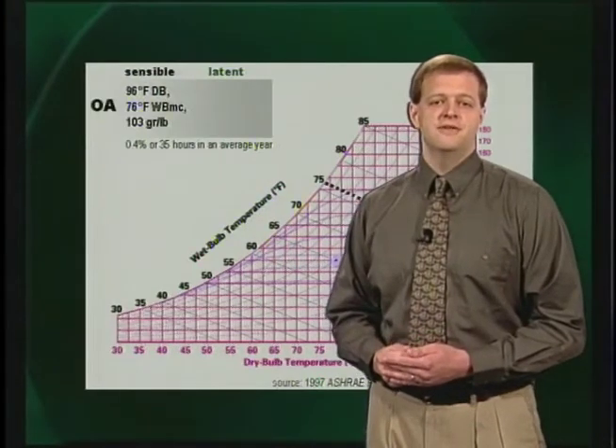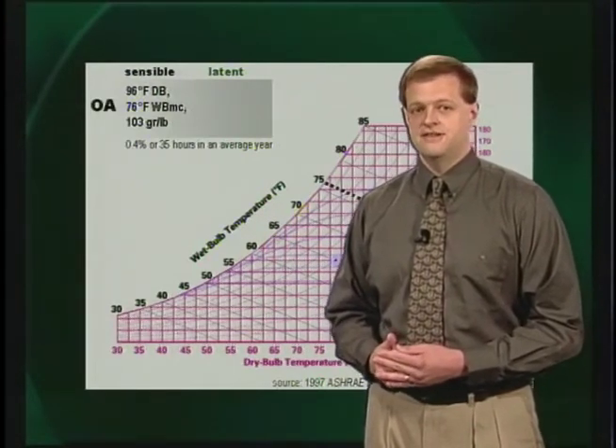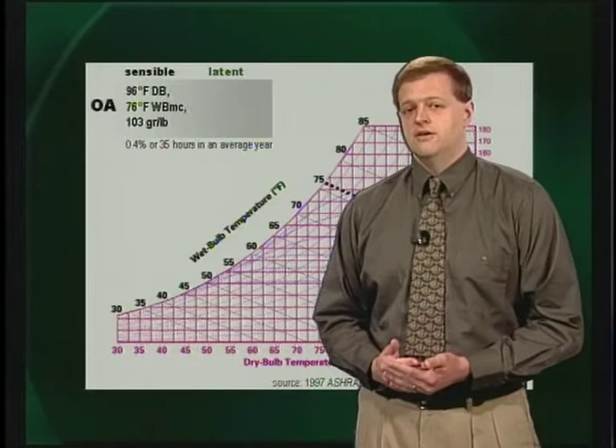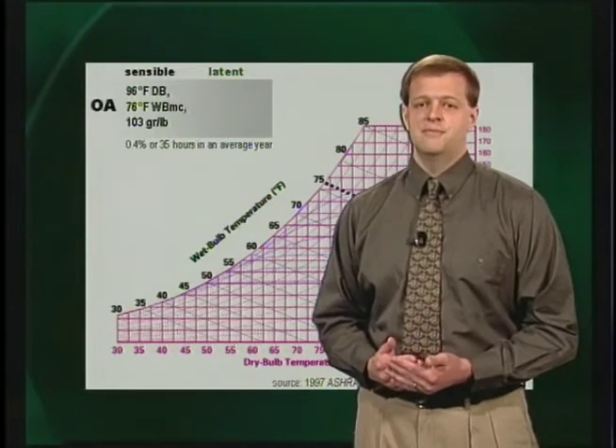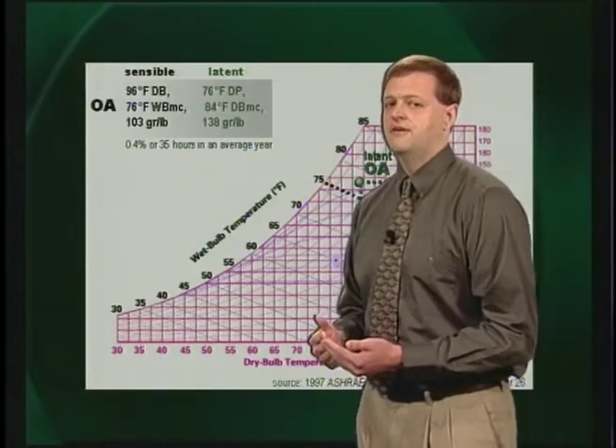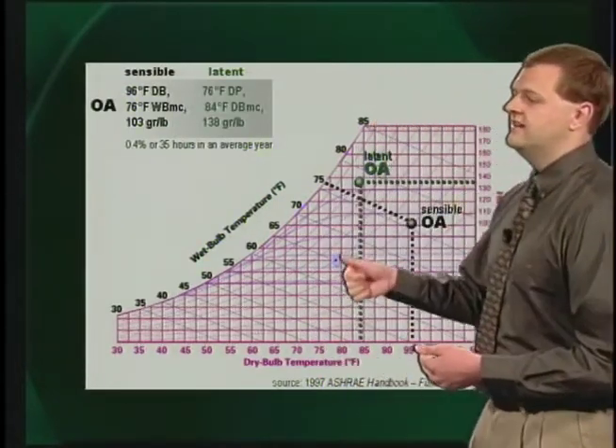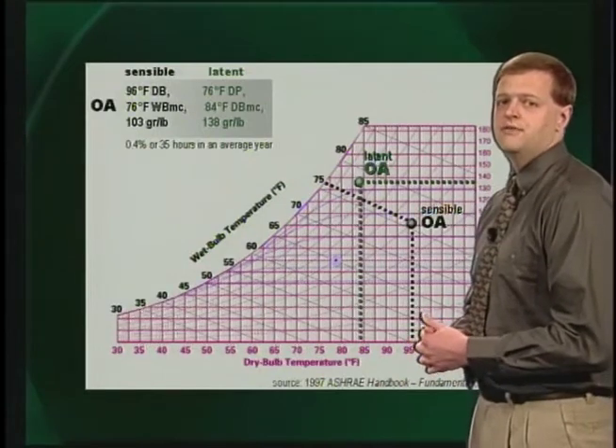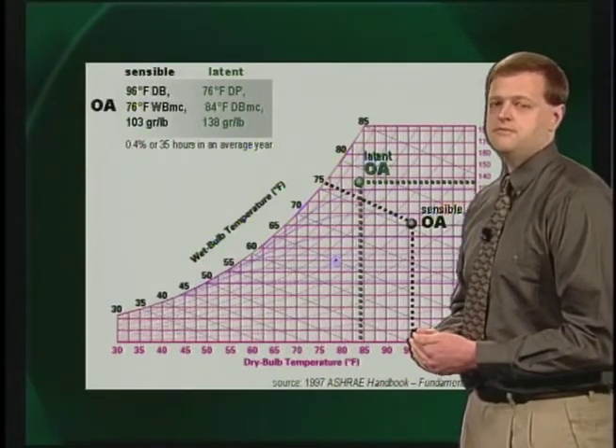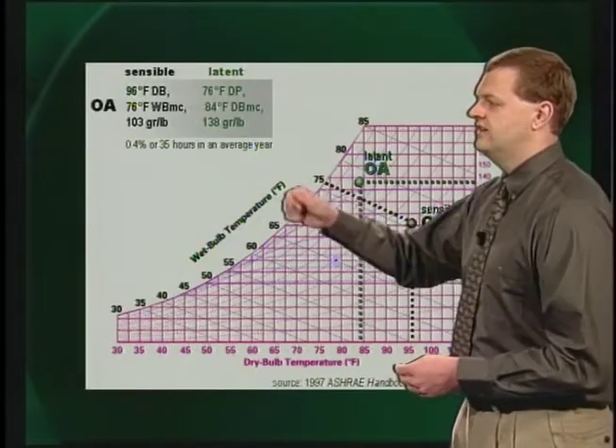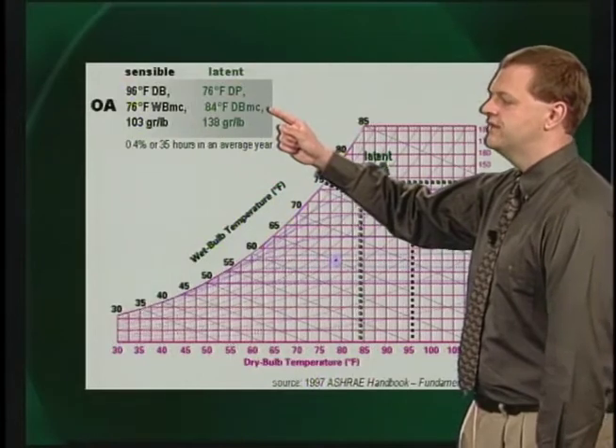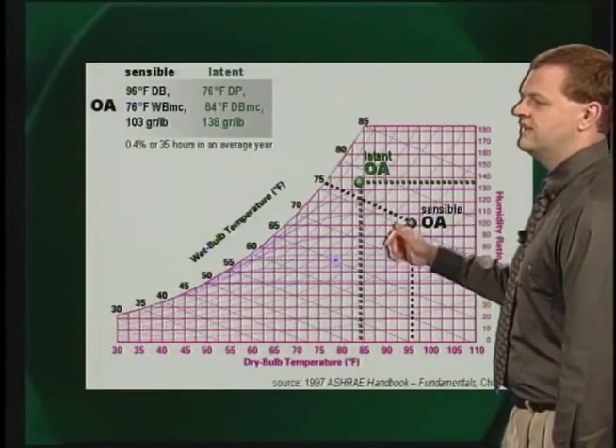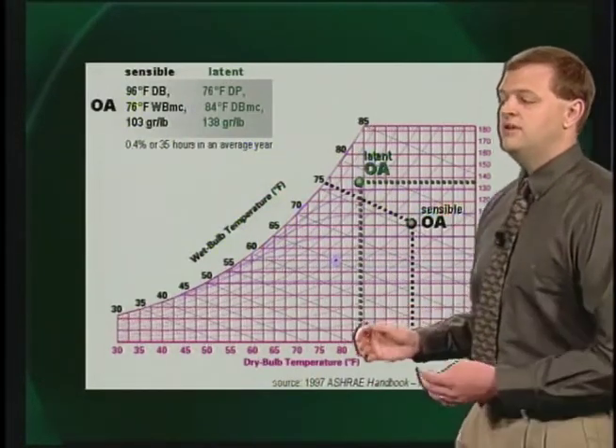For example, the 0.4% sensible design condition is 96 degree dry bulb and 76 degree mean coincident wet bulb. This means that the outdoor temperature exceeds 96 degrees for only 0.4% of the hours in an average year, or 35 hours. In many climates, however, the latent load on the cooling coil is not greatest when the outdoor dry bulb temperature is the highest, but when the humidity ratio of the outdoor air is the highest. This latent design condition was added to the 1997 ASHRAE Handbook of Fundamentals and consists of a dew point temperature or humidity ratio and a mean coincident dry bulb temperature. The 0.4% latent design condition is 76 degree dew point and 84 degrees mean coincident dry bulb.